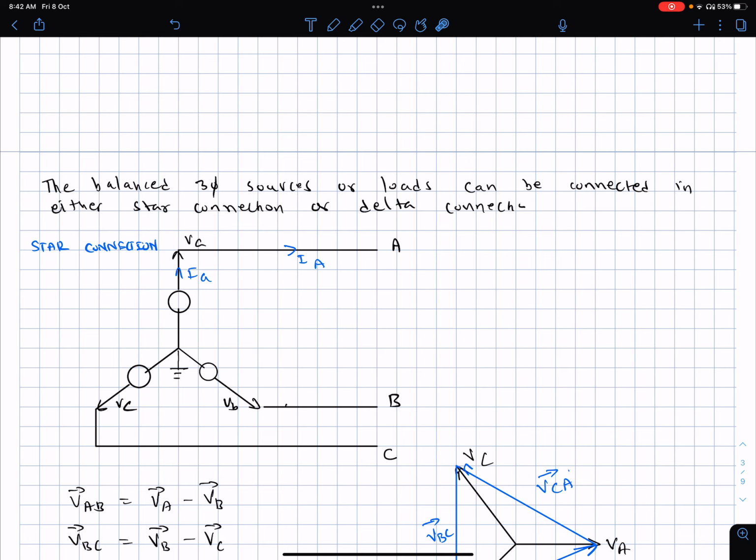If the surface of the machine is also at zero potential, if by chance we touch it, we will not get any shock. Otherwise, if it is ungrounded, then sometimes some induced voltages due to electromagnetic induction may bring something on it, and then we touch it, we are at that potential, and that creates a problem. So directly the first touch will not cause a current to flow, but if there is any other place from which it is grounded, then there will be a loop closing and we may get a shock. So safety requires that we usually do grounding.